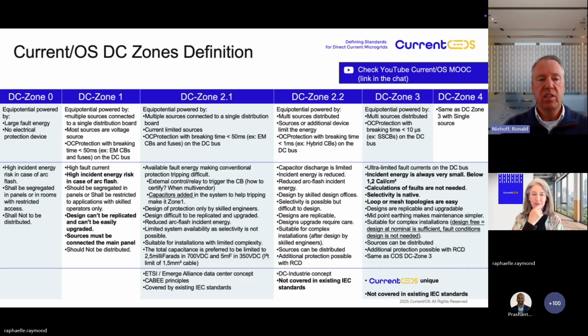And as you can see, it's also a lot related to the type of circuit breakers. On the left side, in DC zone 0, there is no circuit breaker at all. So there is the raw source. And to DC zone 1, you come already in the area where a first protection device is situated. And this could be an electrical, mechanical, a circuit breaker, or a fuse. If you go to zone 2.1, there you have a similar type of protective devices, only the energy is lower. And if you go to zone 2.2, you see that the disconnection time is again lower.